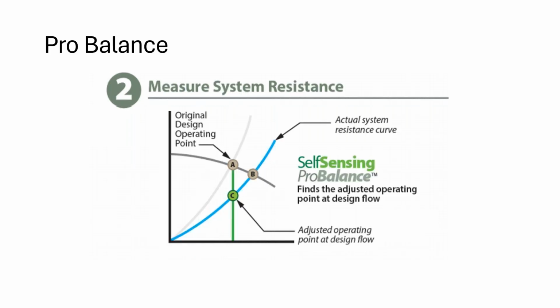So, you know, we know we're out too far. We put it in constant flow mode, back to the flow rate we need, right? You've designed the system, or somebody has, it's on the drawings. You want that pump to run at 300 GPM, 100 GPM, 200 GPM, 1000 GPM, whatever it is. Let it run in constant flow mode, and it's going to show you on the screen what that head loss is actually for that system.